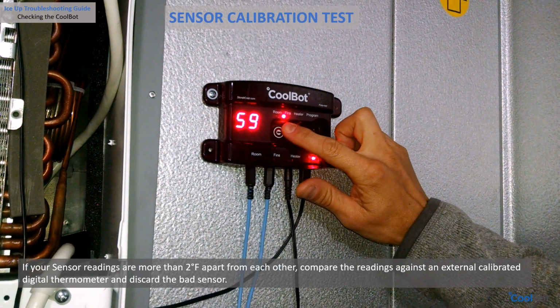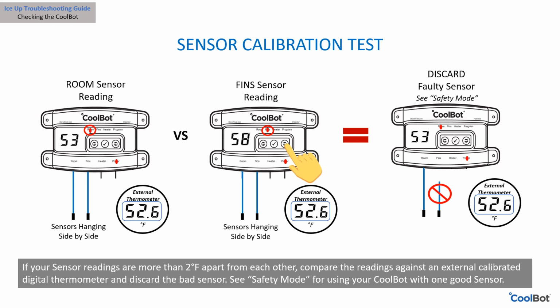When comparing the readings of your sensors, they should be the same or within 2 degrees Fahrenheit. If they are more than 2 degrees Fahrenheit, compare the readings against a calibrated digital thermometer. Discard the faulty sensor and replace it with a new one.